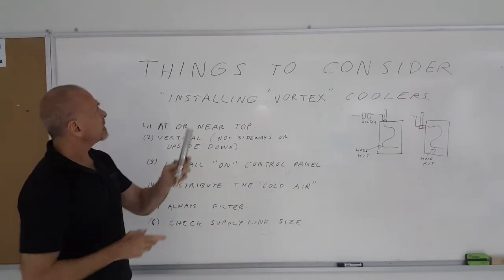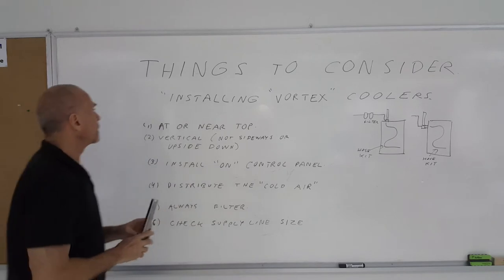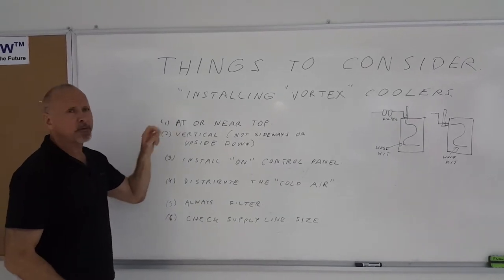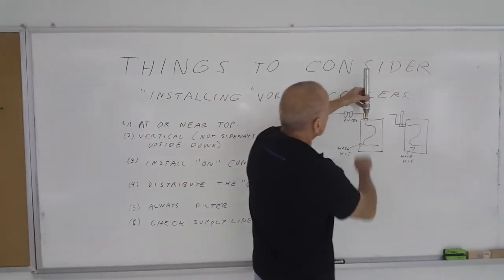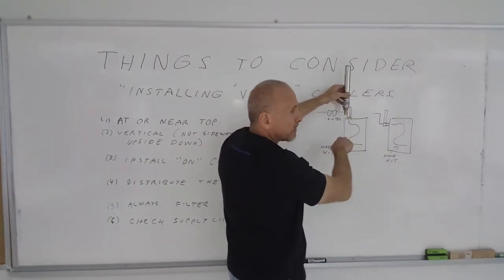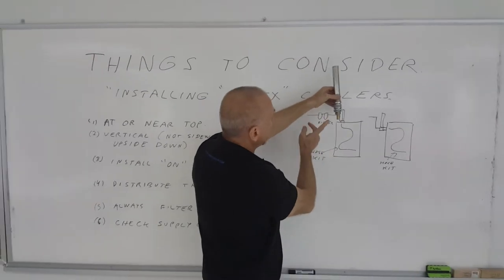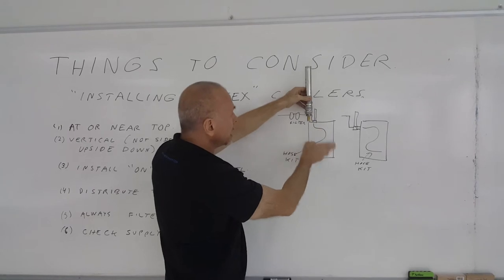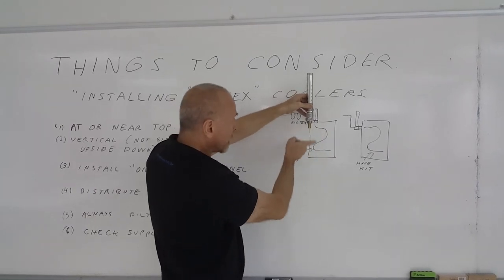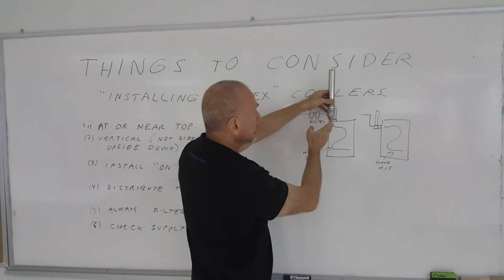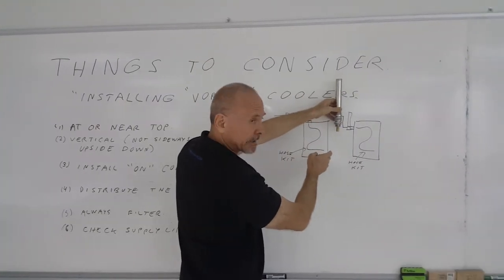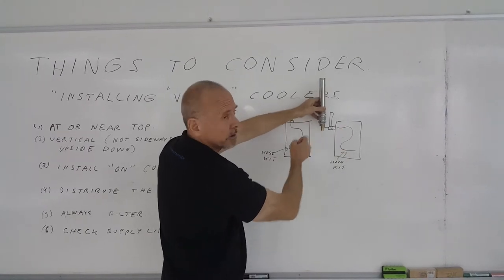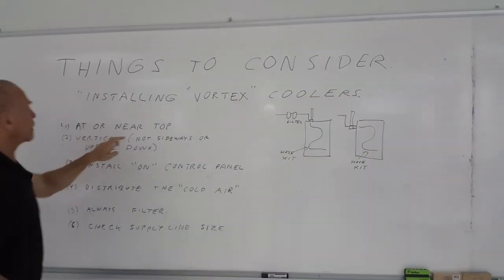Things to consider when installing these vortex style coolers. Number one, you want to have it at or near the top of the panel. The reason is hot air rises, cold air falls. Panel coolers have a vent that's built in to allow the hot air that's being displaced to leave the panel. So you would want to have it at the top, or if it can't be mounted at the top, utilizing a side mount, it can be mounted near the top on the side, still allowing for the hot air to come out.